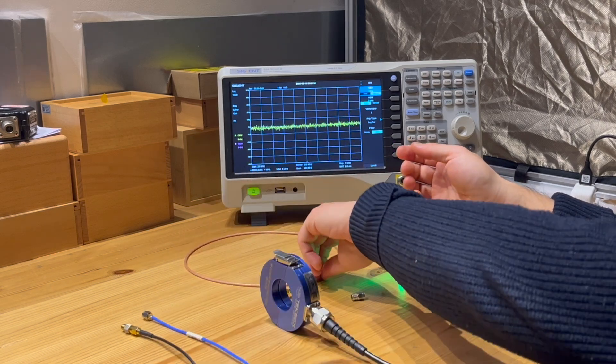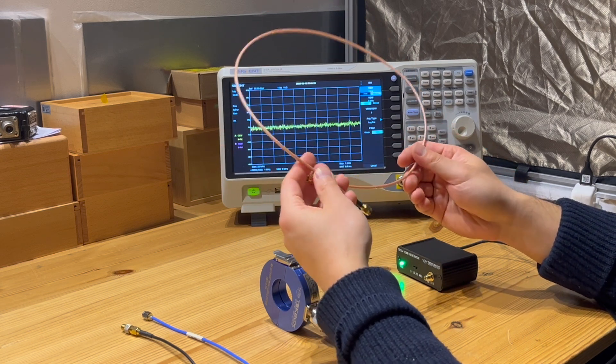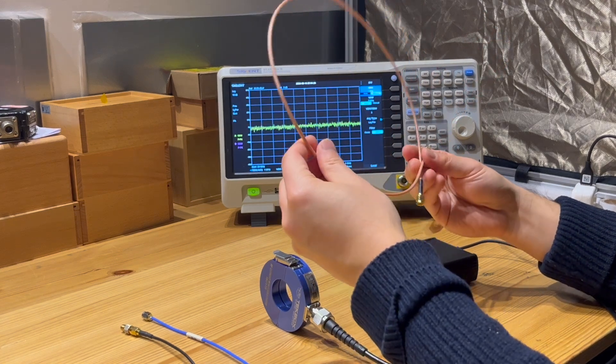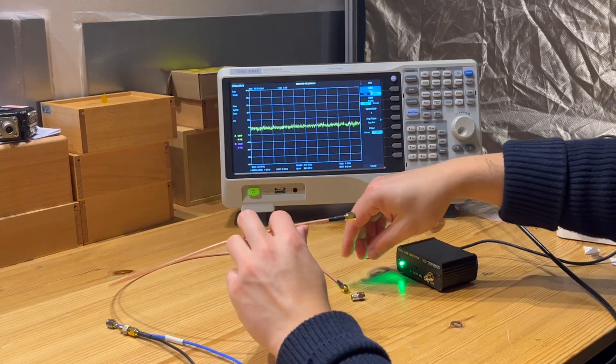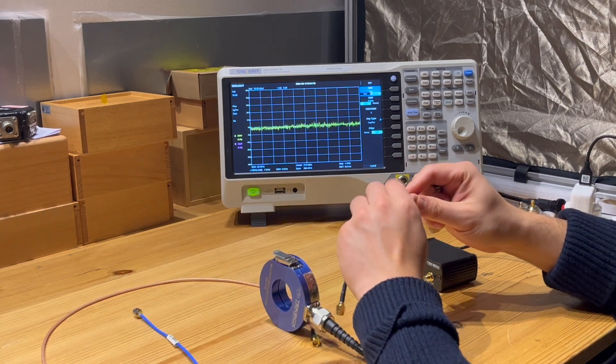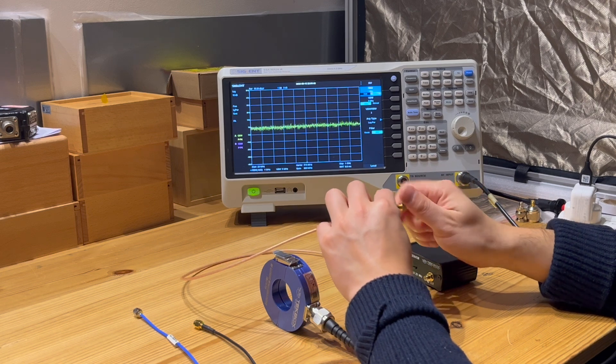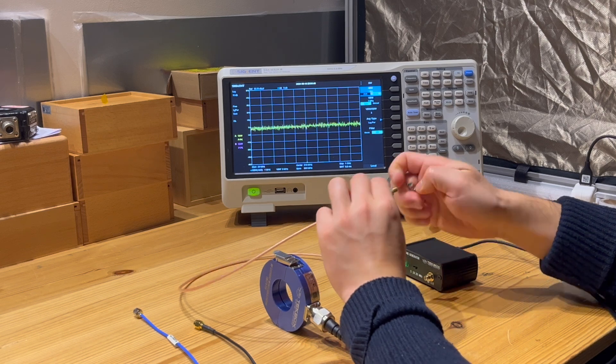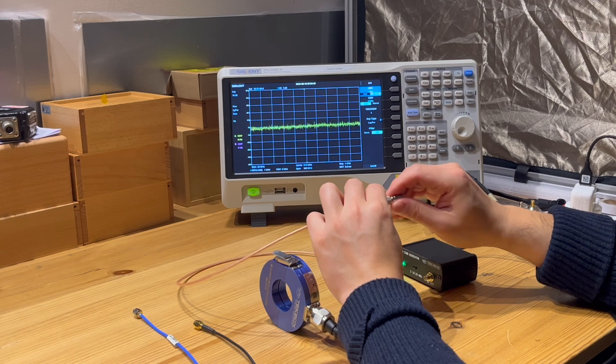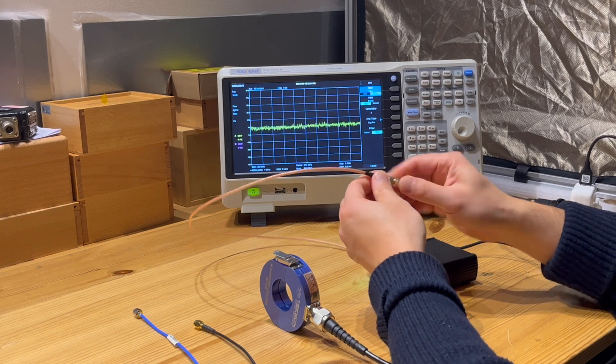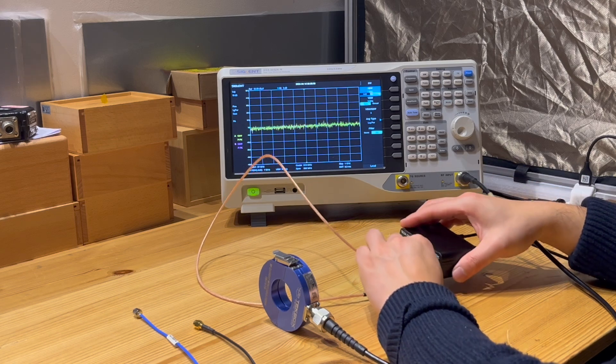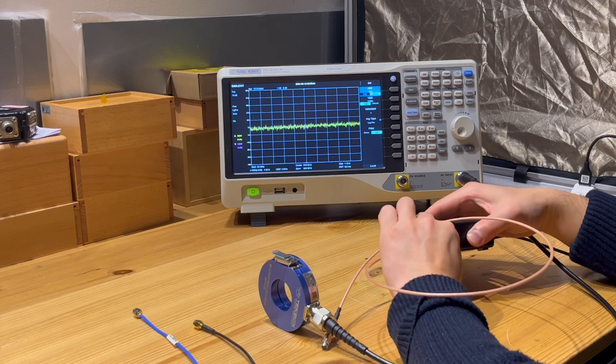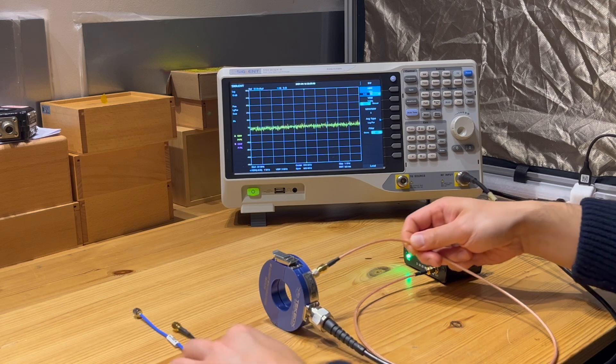And this is again a typical coaxial cable. We're going to test the performance of each one. Shall we start with this one then? Okay, so this is a long cable so I need to terminate one end using a 50 ohm terminating resistor. To perform the test, it's important to ensure that the connector with the load has a really good grip here - no loose connection on this end and also no loose connection on this end.